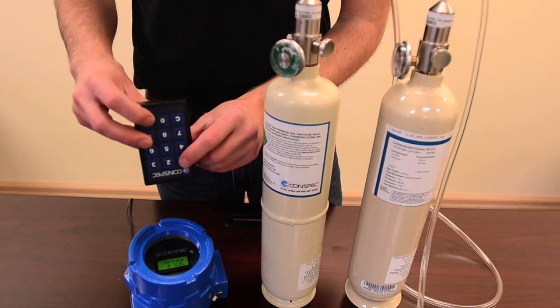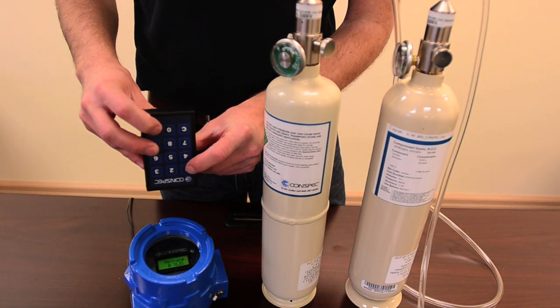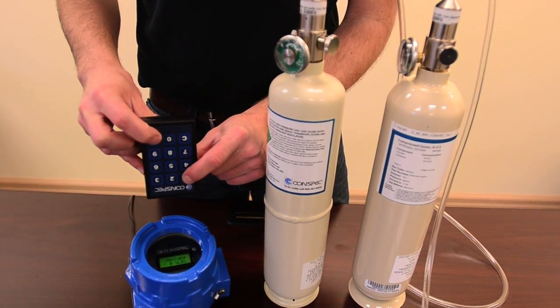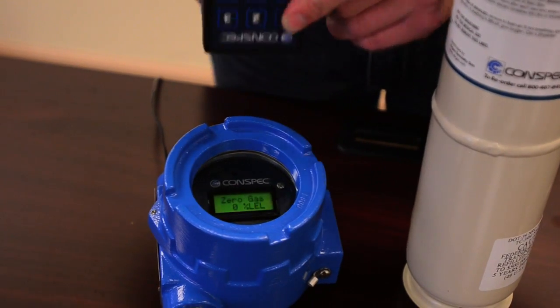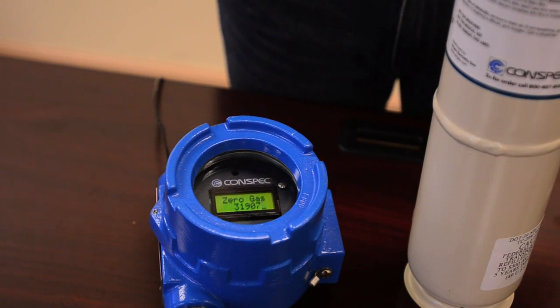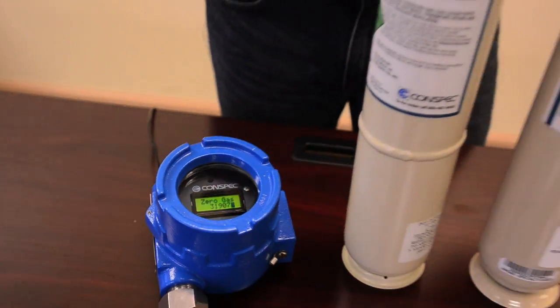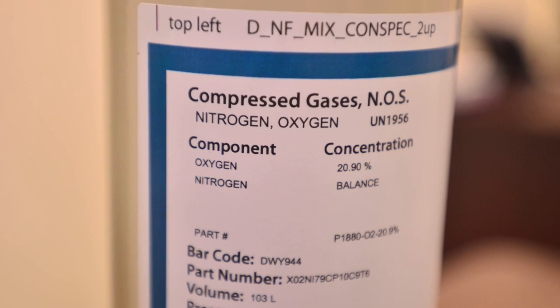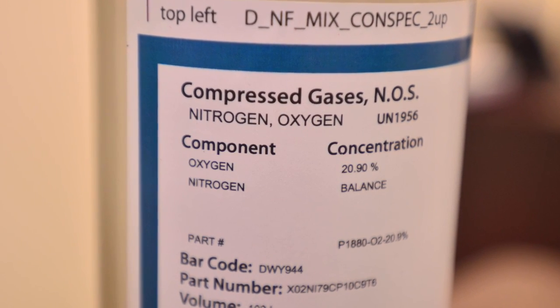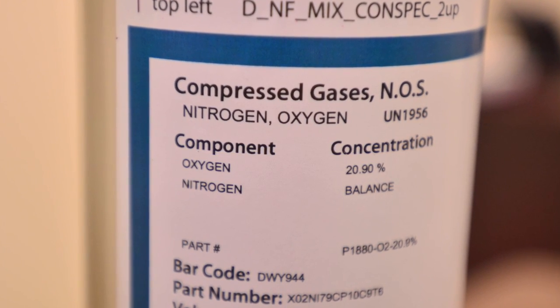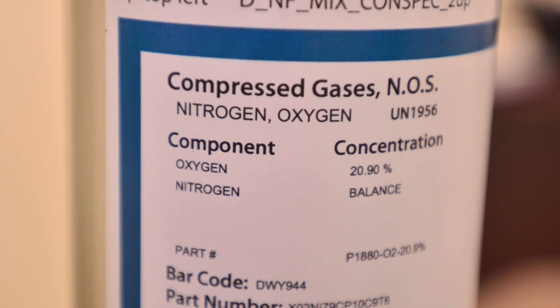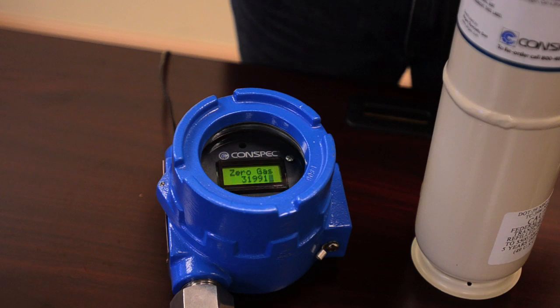To initiate your calibration, you want to enter the function 111, 3 ones, and the monitor will ask for zero gas. This time we can turn on our zero gas. And since this cylinder contains a gas that's very similar to our ambient atmosphere, you may not see much of a change in the number.